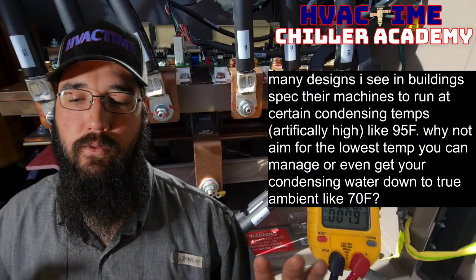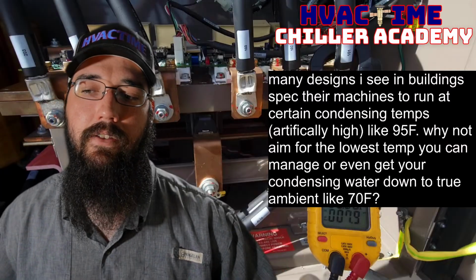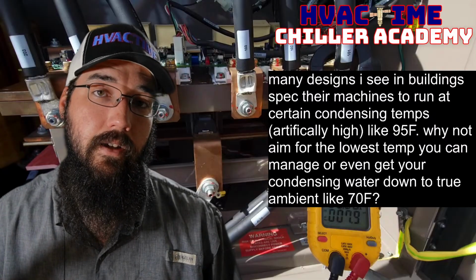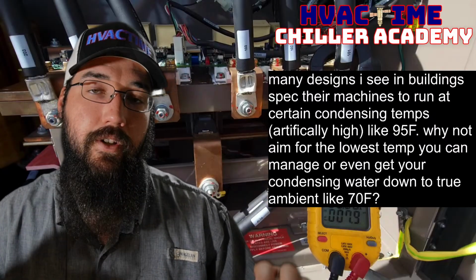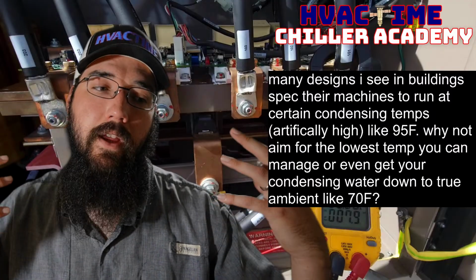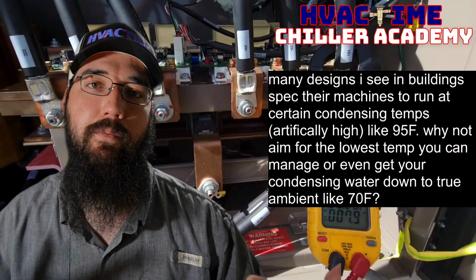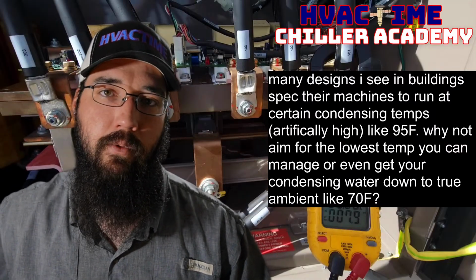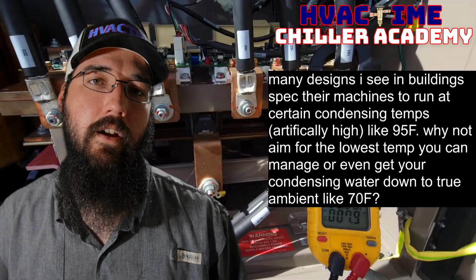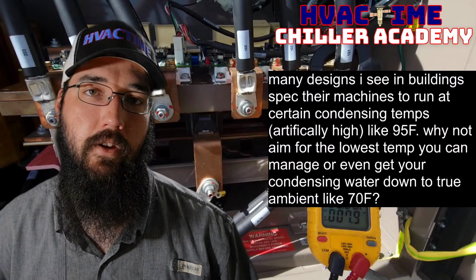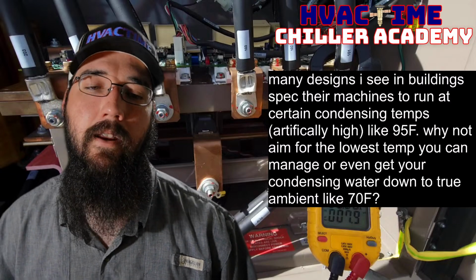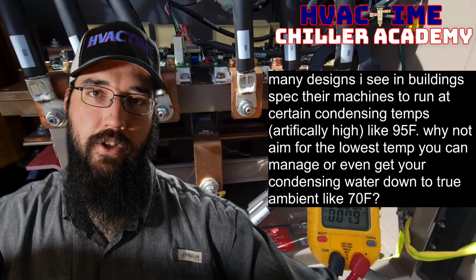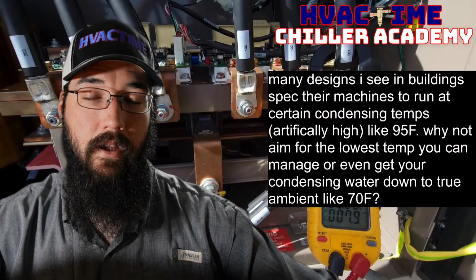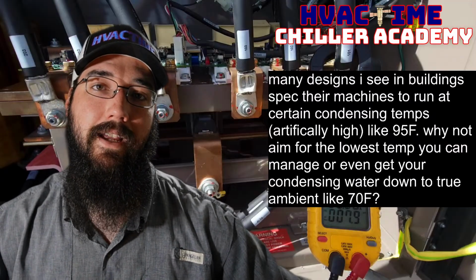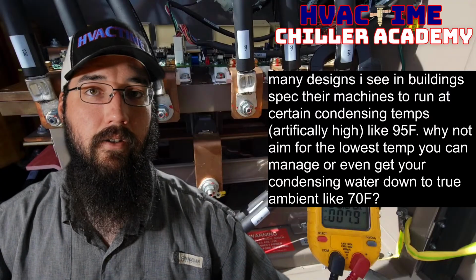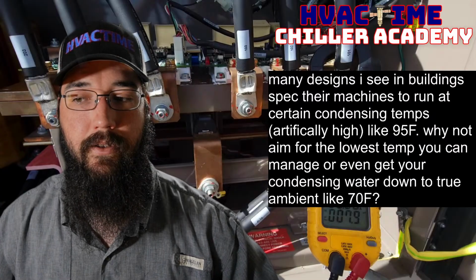And what ends up happening that I have seen is they'll do these things and they will end up showing where they've reduced the total energy usage of the building. And so they have this positive feedback loop to think that, okay, well, by setting that high condenser water set point, that ended up taking a lot of load off. That was part of the bigger picture to take the load off, and we're now more efficient because of that. When in reality it's all the other things that they changed to help that building operate better that did lower the energy profile, but they did end up increasing the chiller's energy profile because of that condenser water set point.